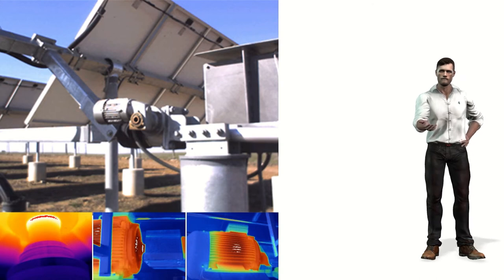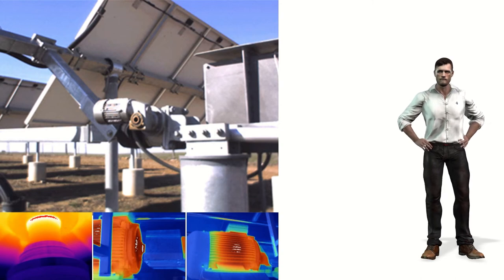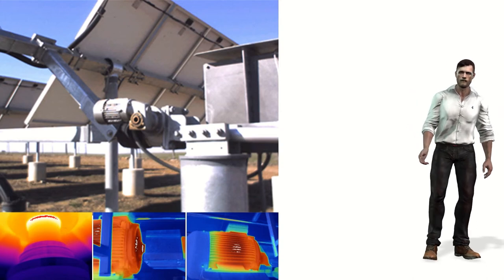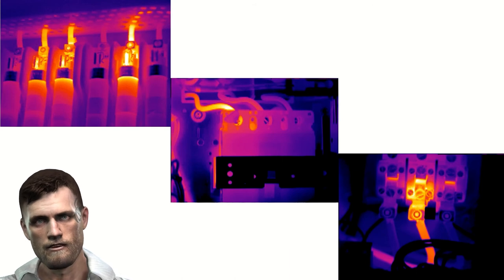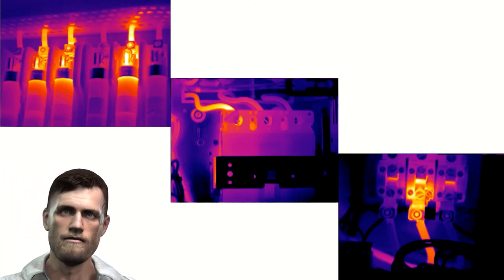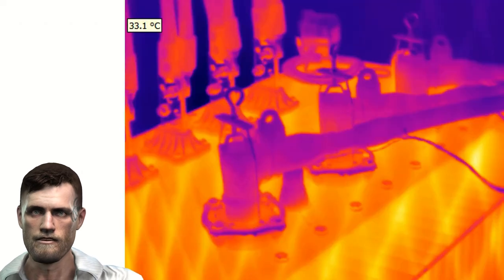In a photovoltaic installation there are not only panels but also other electrical or even mechanical elements we can inspect at a thermographic level. Motors in industry are typical elements in any thermographic inspection program. However, in a photovoltaic installation the motors associated with tracking systems may be more difficult to inspect since they do not work as intensively. We can inspect the wiring, connections, or protections and detect hot spots associated with poor power tightening or even overload and harmonic problems in the cables.